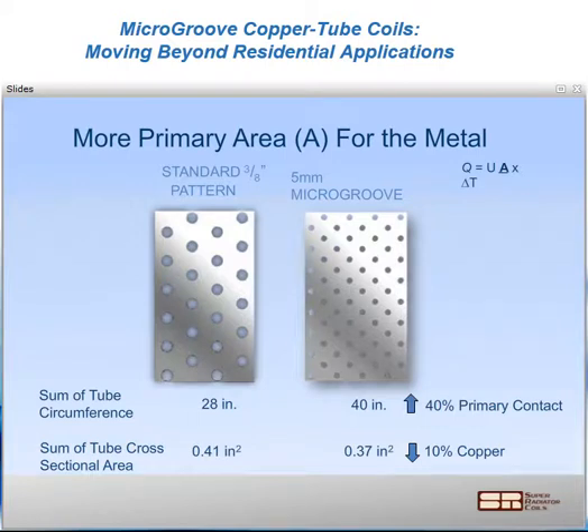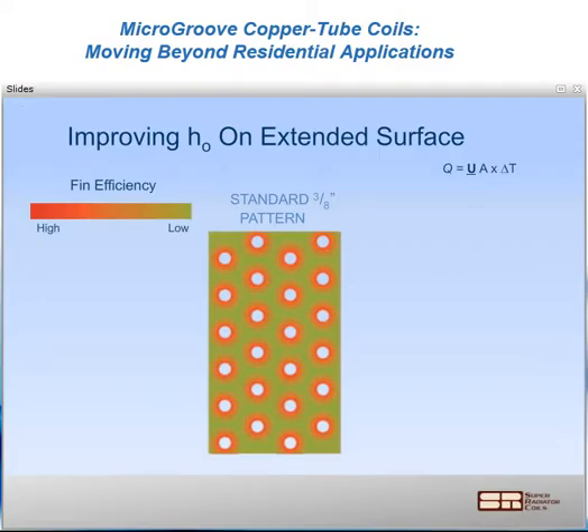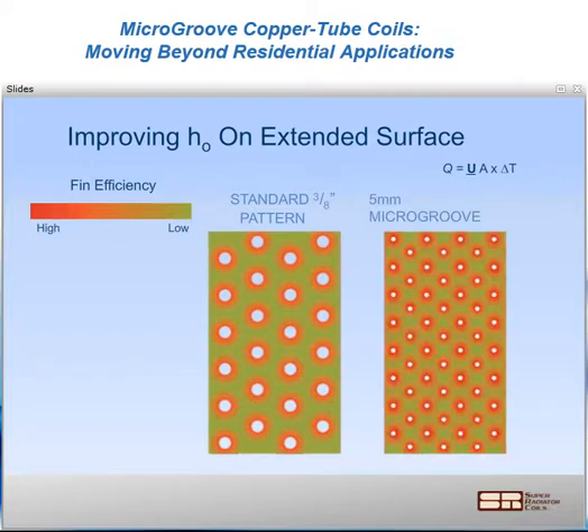If we run with that further to look at that compounding benefit and think about fin efficiency, here again is our 3/8 traditional tube pattern. This illustration shows the reduction in fin efficiency as you move away from the primary surface. You diminish the effectiveness of the fin in its proximity to the primary surface. You see that in the color coding, and then when we compare it to our 5mm, you see the additional red and orange coloration on that extended surface. We're getting a lot more work out of our extended surface by keeping it closer to the primary surface. This is where we see driving up the overall average coefficient use of that extended surface. A lot more work out of that fin.